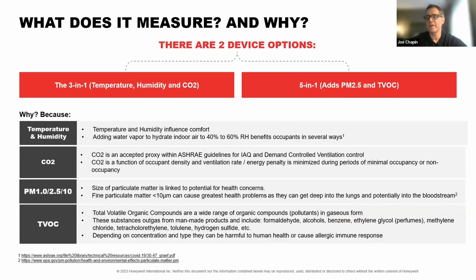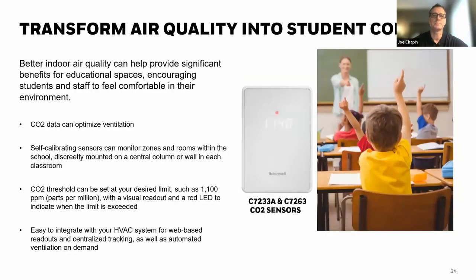One of the solutions we have implemented is to put a TVOC sensor in the air intake. Once it started sensing the fumes coming into that room, it shut the outside damper and brought air from the other side. This is all done automatically, by the way, via a control sequence. So they eliminated the problem of that particular room with the bus fumes. This can be a metal shop, things of that nature, as well. So again, there are a lot of things you can do with this when it's connected. By itself, it's a great unit, but by connecting it, you can build in the automation as well.